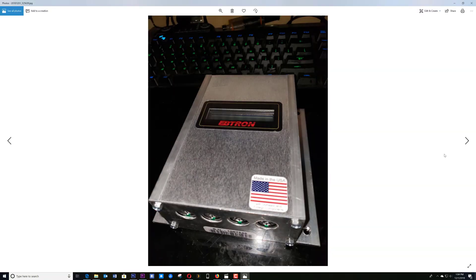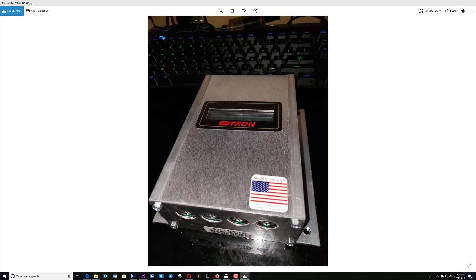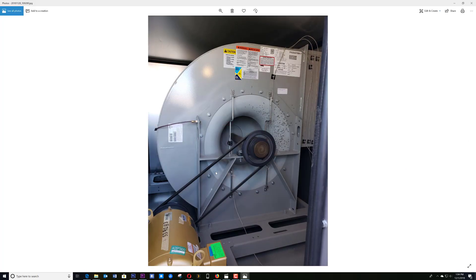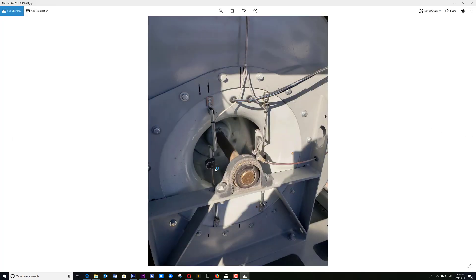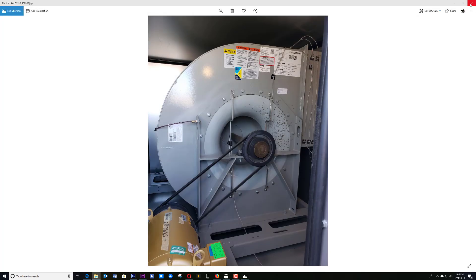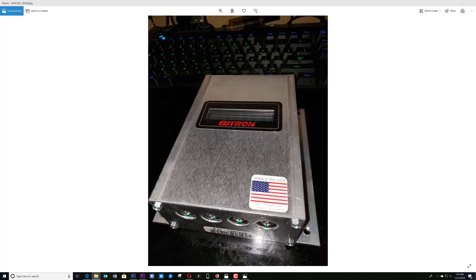this is an airflow controller. It has these four ports on the bottom that you plug in to these four sensors. The four sensors are hooked up to this big return air blower, two on each side, two right there, and then these two on the other side. I took the four old ones off and put four new ones on because that was the new kit that I was given with this controller.